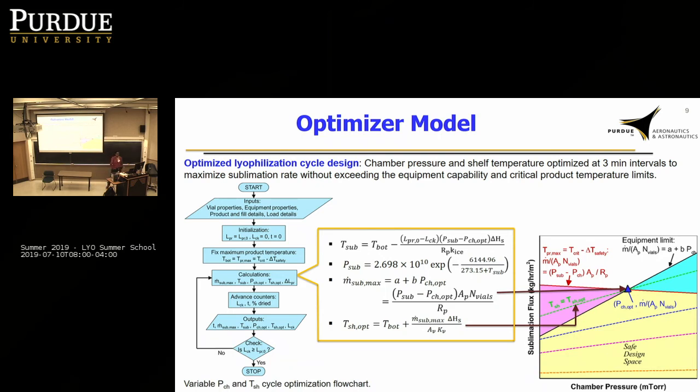Now, how you know that is you can do experiments. You can do just in a tray, you can load water, you can run that experiment, or you can run CFD simulations, because it's been demonstrated in plenty of papers that that's pretty simple to do. As long as you know your geometry, you can run a CFD simulation and extract that equipment capability. Or I don't know, your vendor might be able to provide it to you if they have done those experiments.